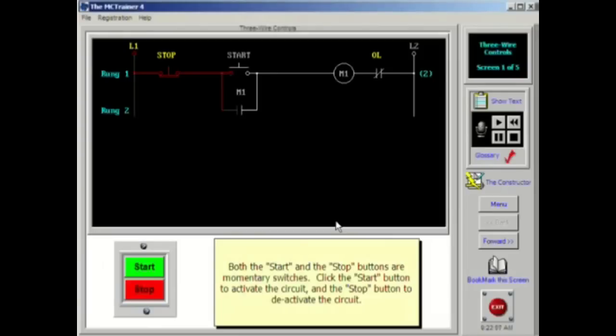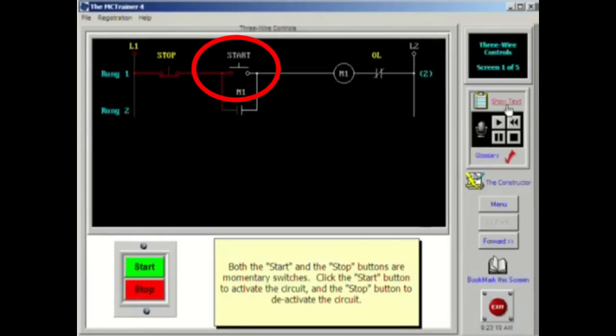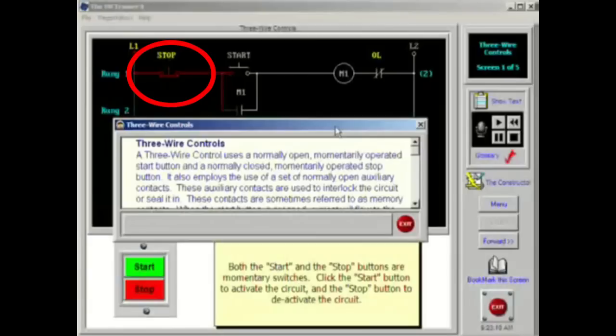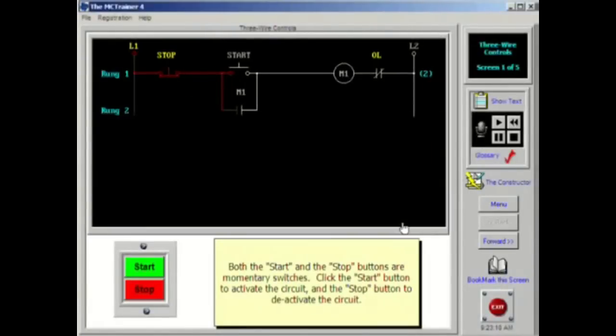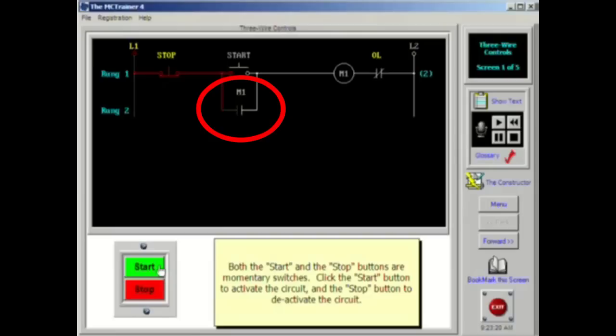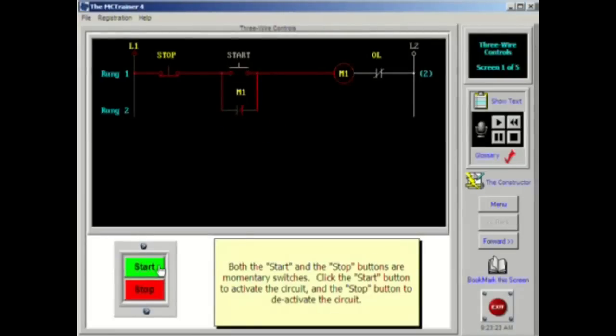A three wire control uses a normally open, momentarily operated start button. It also employs the use of a set of normally open auxiliary contacts. These auxiliary contacts are used to interlock the circuit or seal it in. These contacts are sometimes referred to as memory contacts.